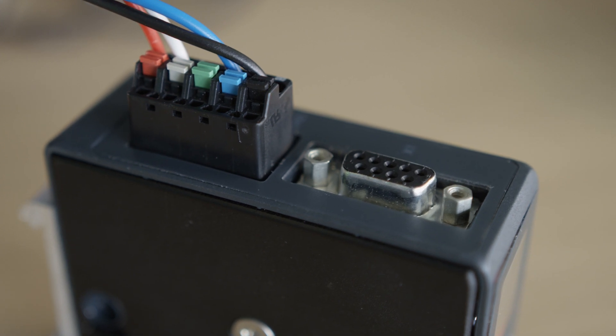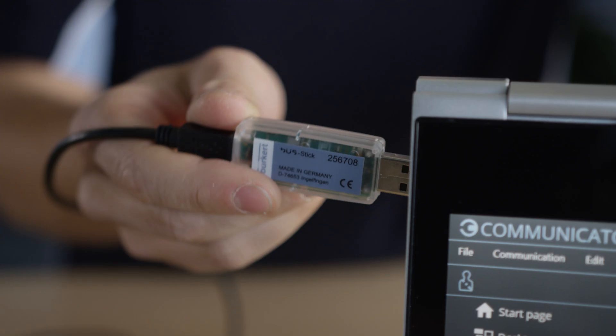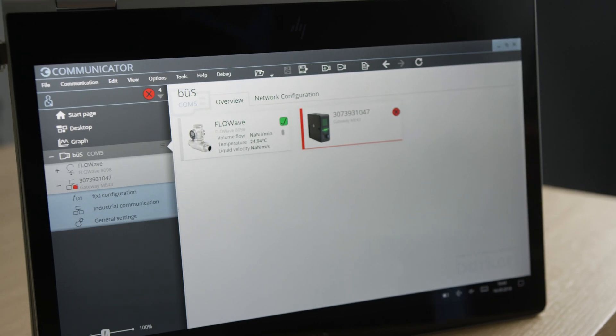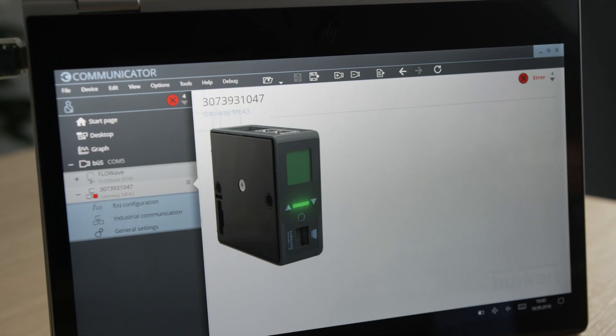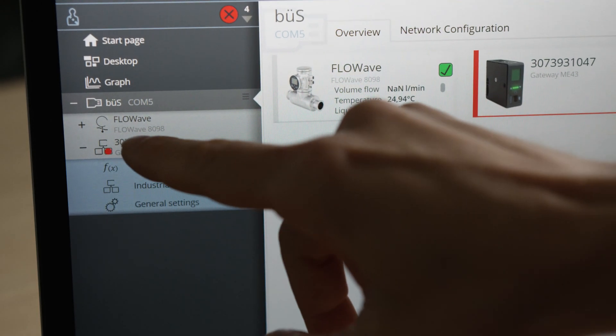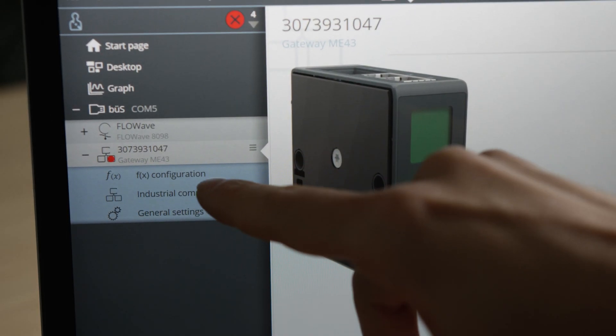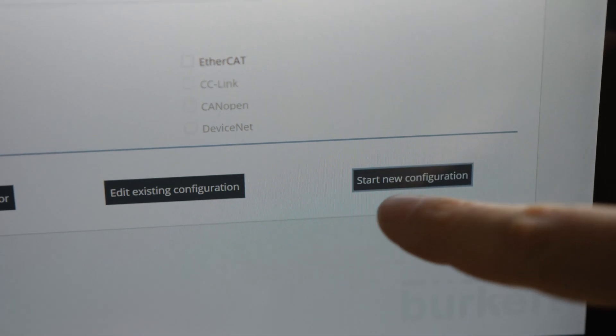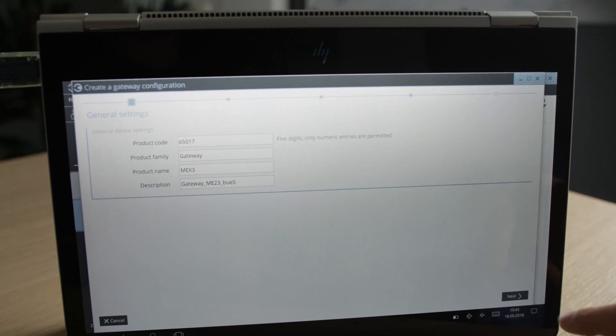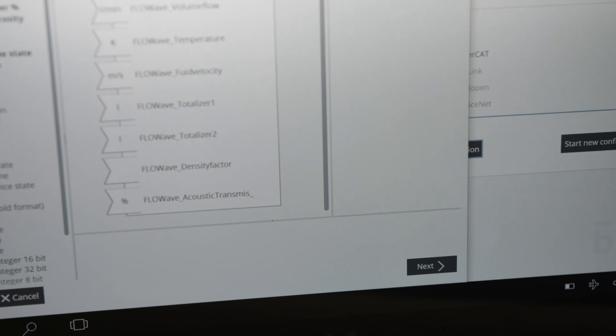Firstly, the ME43 must be configured for PROFIBUS to connect FLOWave to a controller via PROFIBUS. The individual steps for configuration of the PROFIBUS Gateway are as follows: Industrial communication, create a gateway configuration, start new configuration, next, connect inputs and outputs, save and finish.